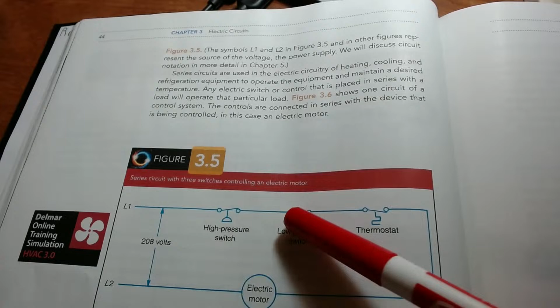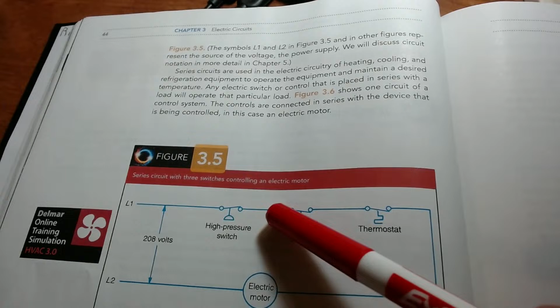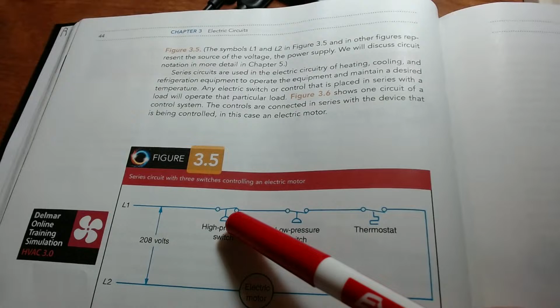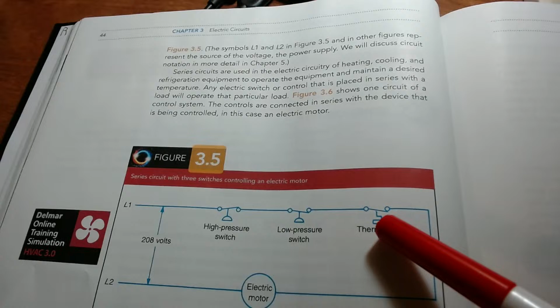If one fails, it kills everything. So if I lost my low pressure switch, I'd have power through my high pressure into my low pressure and nothing out of my thermostat. If I had power in my high pressure and it opened up, I wouldn't have any voltage going that direction. So this is where it's got to go in series. Everything goes straight through.